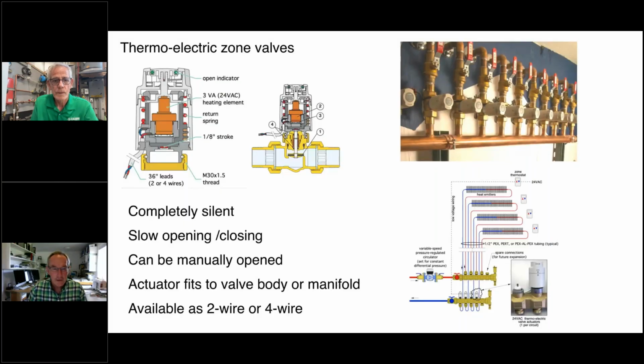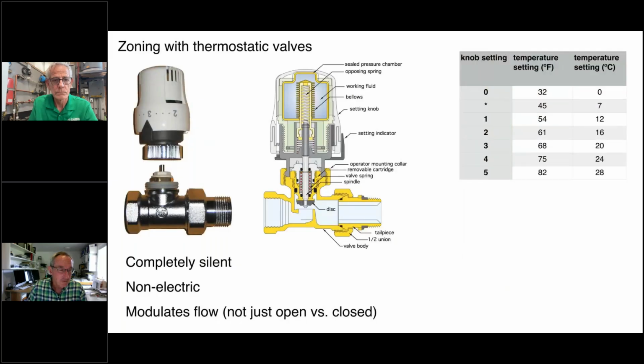Okay, let's get away from electricity and go to thermostatic. Now, again, no power involved. We've got a valve body here that's got a spring-loaded linear shaft. This is not a rotating shaft. The spring holds the valve fully open. When you screw this operator on here, it's going to push that shaft down and close it.